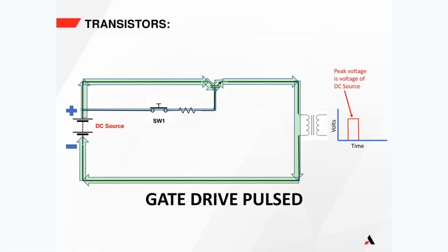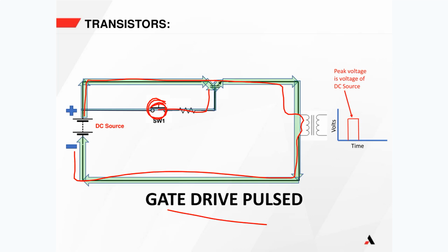If we do send a signal to the IGBT by closing this switch, then power will flow from positive all the way down through this transformer back down to negative. So if we just press that button quickly and pulse it, we are going to get a square wave that has a peak voltage of whatever this DC source is. And remember, it's 135 volts DC because AMETEK SCI UPSs are more often than not connected to a 60-cell lead acid battery. So this peak here would be 135 volts DC.